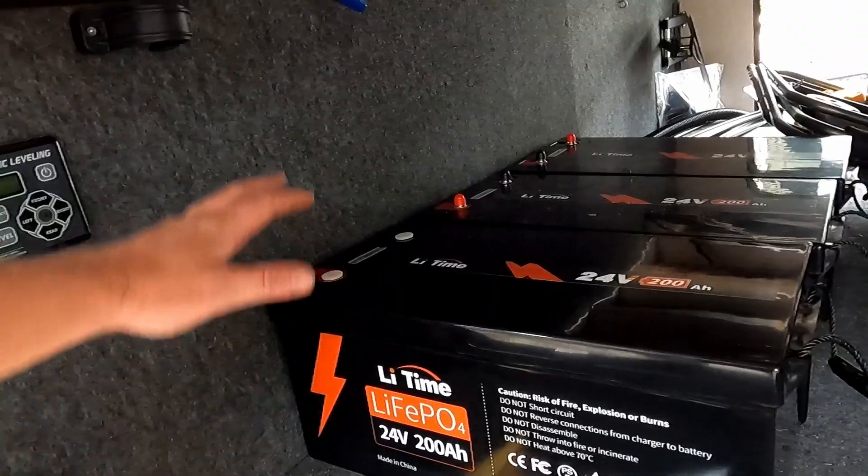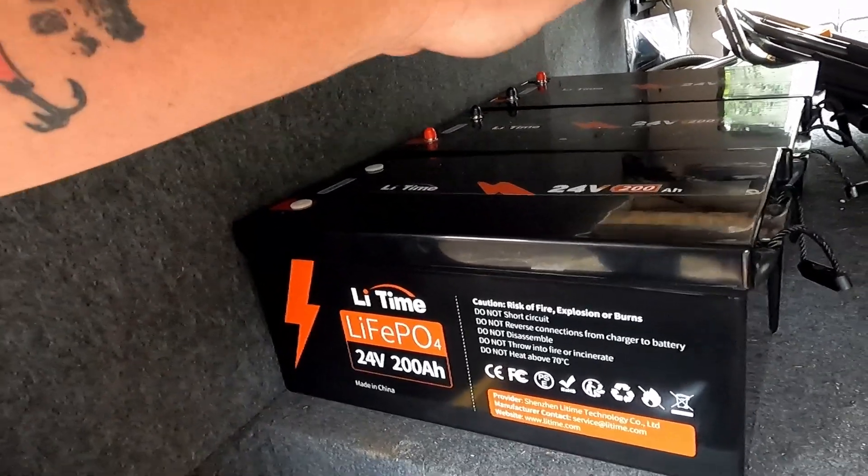We have all of that in a playlist on our channel if you want to check it out. We have three 24-volt 200 amp-hour batteries — in 12-volt terms that's 1200 amp-hours. We decided to go with a 24-volt system because it's half the amperage, so you can use smaller wire, less charge controllers, it's easier on the solar. By doubling the volts you cut the amps in half for the same amount of power. But today we just installed that parallel system and we want to run a test.